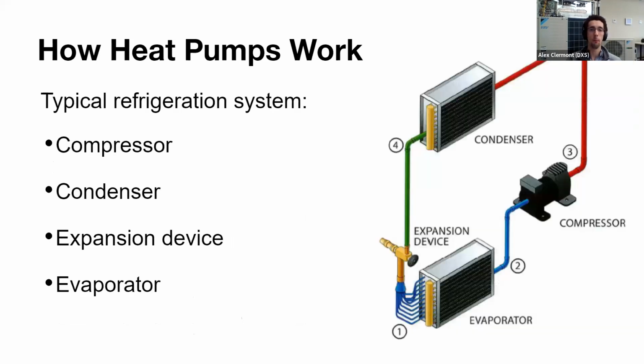Now, it's actually 4 components. You might have seen this before, but it's 4 basic components to any refrigeration system. And it's a compressor, a condenser, an expansion device, whether that's a thermal expansion device or an electronic expansion device, and an evaporator. In some heat pumps, the expansion device lives in the condensing unit, such as a mini split, while in other devices, such as VRF, which we'll get into, the expansion device actually lives in the indoor unit.